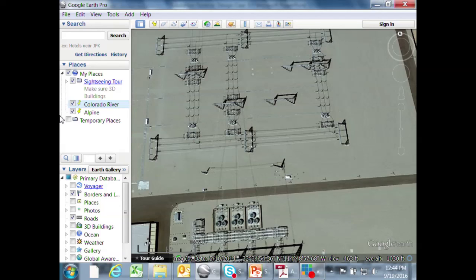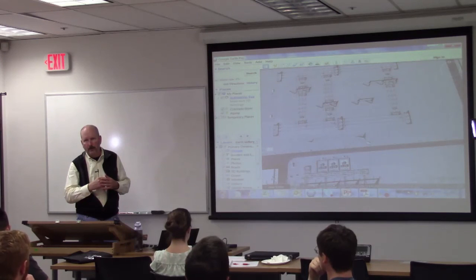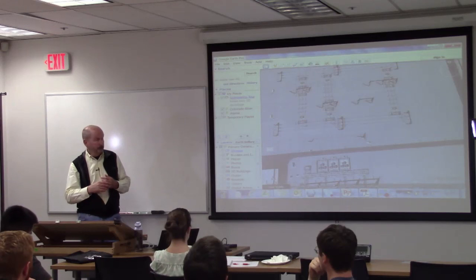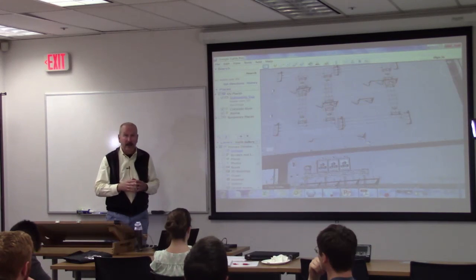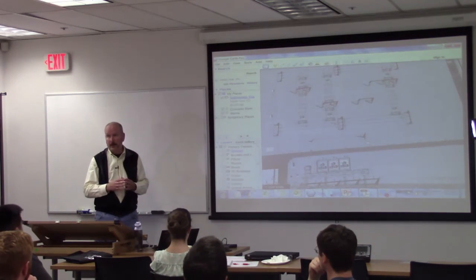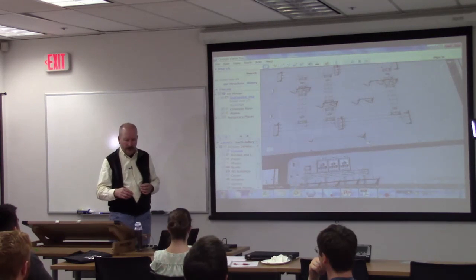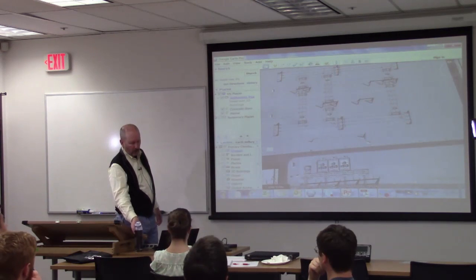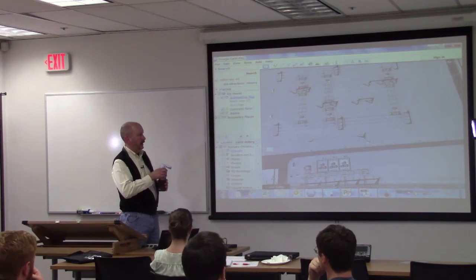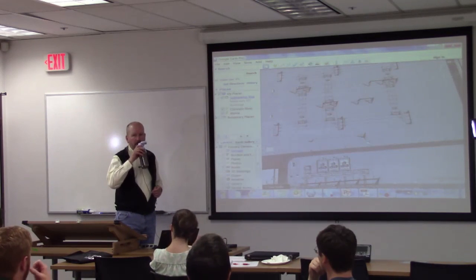One other aspect, and then we'll wrap up. Some people like to embed conduits in foundations and have the conduit come up right in the right spot so it goes into the control cabinet. You'll probably see that in some of your designs. I recommend against that. It's just another thing to get screwed up on your project, whether we make the mistake or people make the mistake out in the field. It's a mistake waiting to happen.